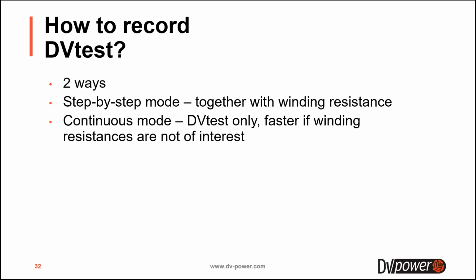So how does it work? If you're in the first tap position, you will inject a DC current, you will measure the winding resistance. When the winding resistance is measured, you keep the DC current flowing through the winding and through the tap changer. You operate the tap changer from first to second position, and during that movement, you record the DVtest graph, and you will obtain that information about the transition from 1 to 2. And when in the second tap position, you again get back to measuring winding resistance, and after that, again, you measure the DVtest, and so on. That's why it's called step by step. So in the first step, you measure winding resistance, and then you record the DVtest. Then again, winding resistance, DVtest, winding resistance, DVtest. So you go step by step.